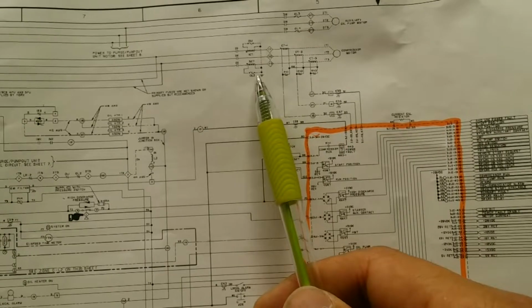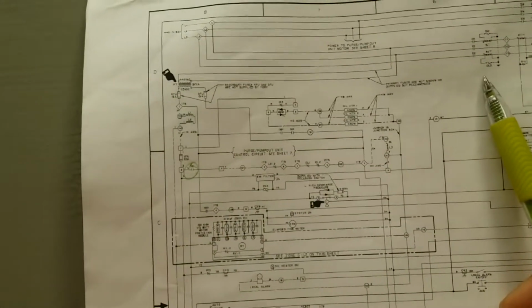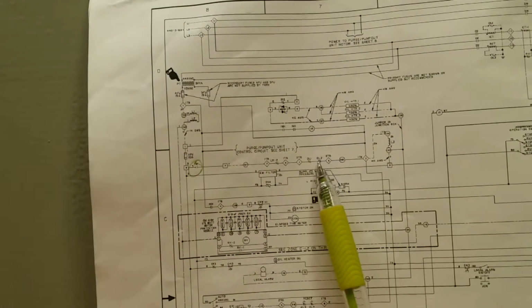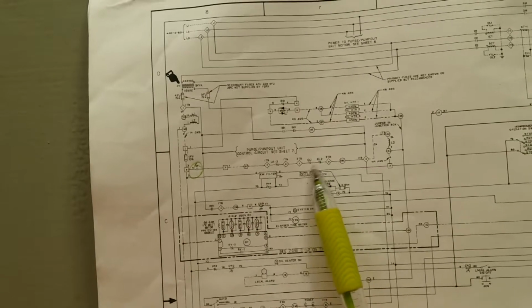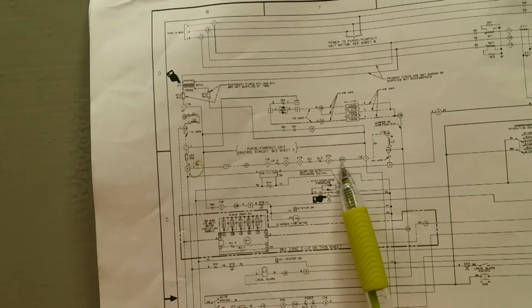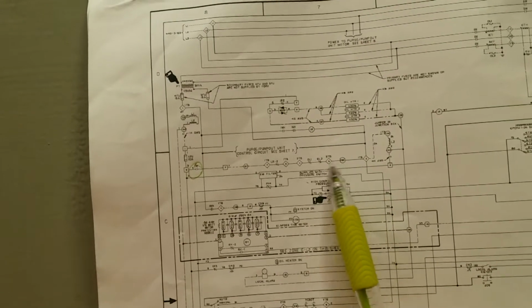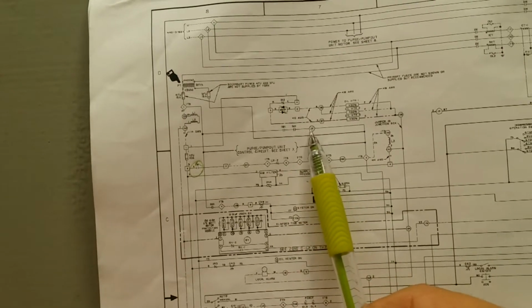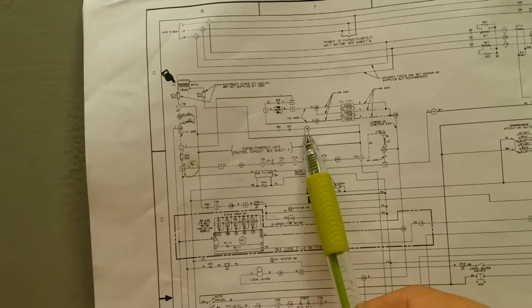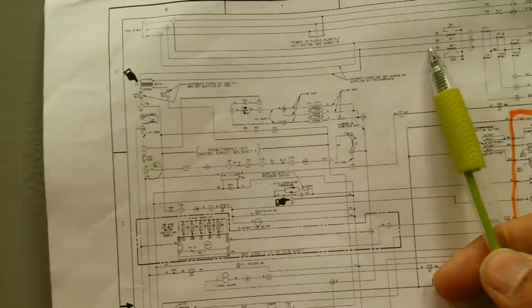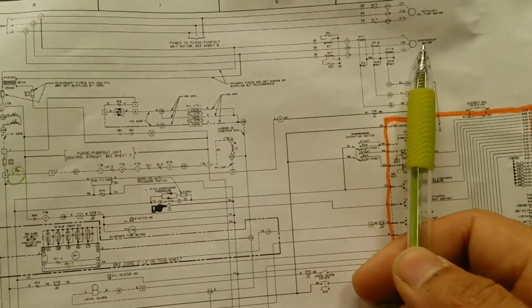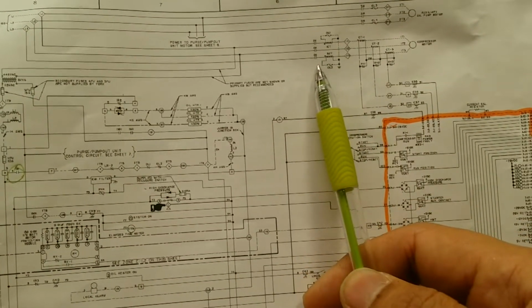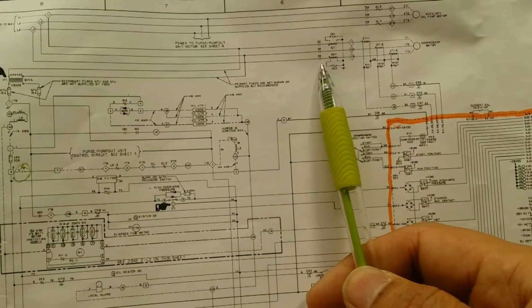If the overloads get too hot, then obviously these contacts over here, one of these 2, whether it be 1 or 2, will open, and it will de-energize IMX. IMX is directly in series with 1M, which happens to be the motor controller or the bed compressor contacts. So that's how that protection happens.